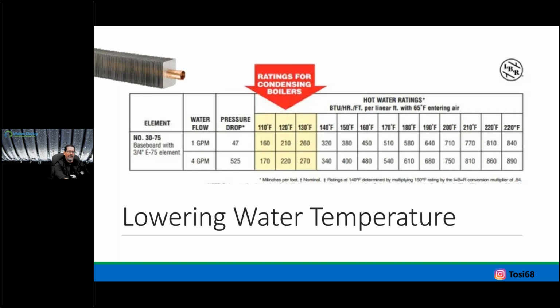And every time the boiler fires and a circulator comes on and that zone calls, I'm overheating the space, regardless of a design day or a mild, 35-degree day in the winter months, right? So now short cycling and efficiencies, it just all goes snowballing in the wrong direction. What we can do, even taking advantage of something that's been installed, inherently grossly oversized, is lower water temperature. Again, if it's cast iron, I don't want you to go below 140. So let's just use that mark.